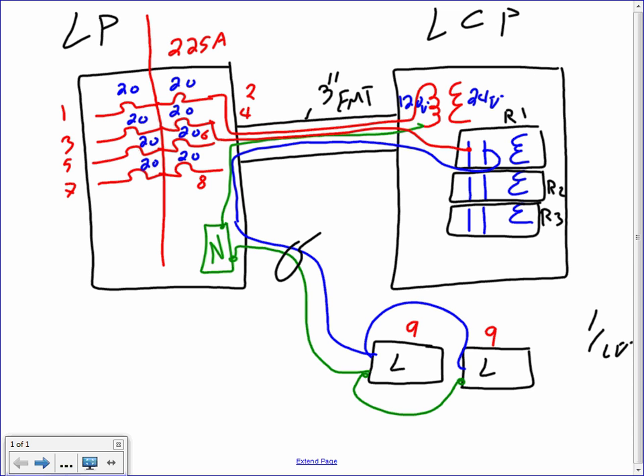This will be 2 conductors number 12, in an EMT conduit, coming all the way to feed the fixture. We got it, this is easy. So when you label these in Revit, they'll be labeled circuit number 4 feeding them.